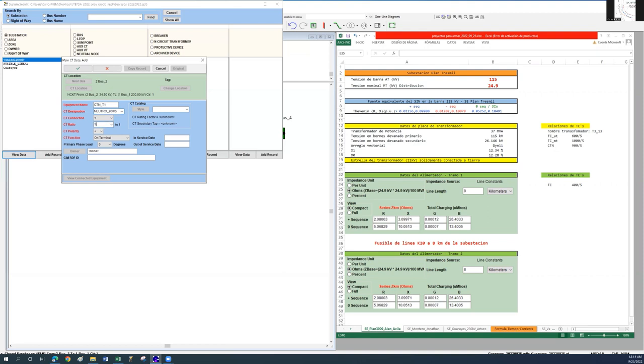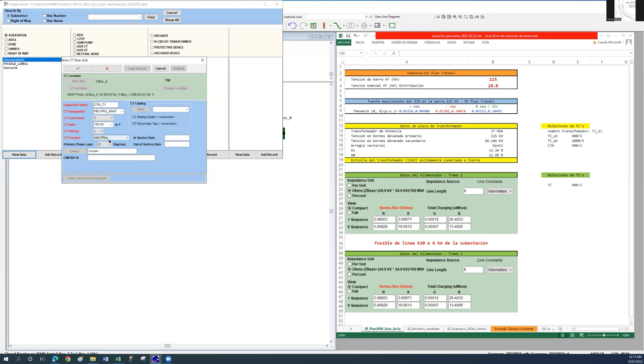In the CT ratio field, put 180, which corresponds to the 900 to 5 ratio. In CT function, choose neutral, because it is a single CT mounted at the neutral of the Y grounded winding.